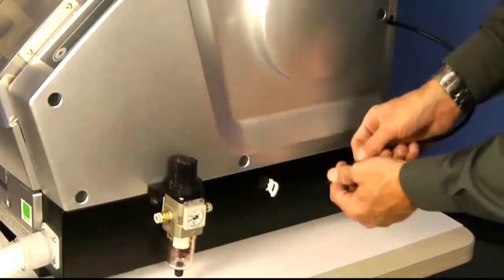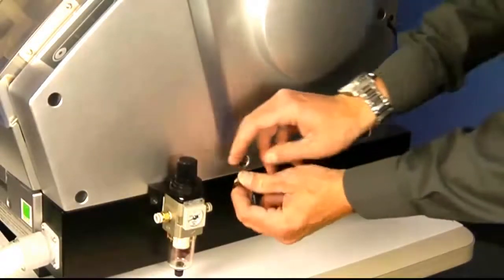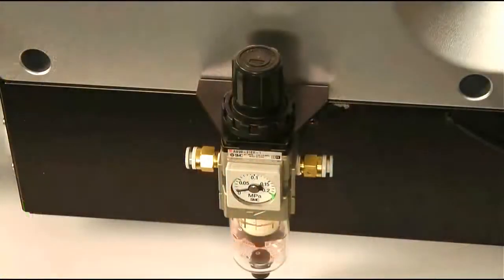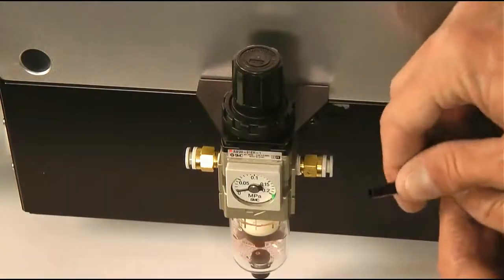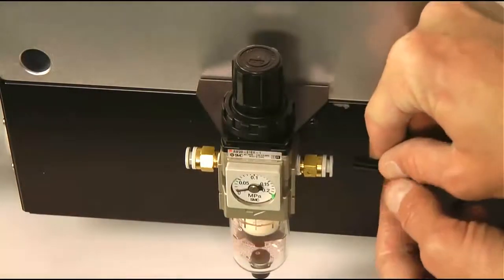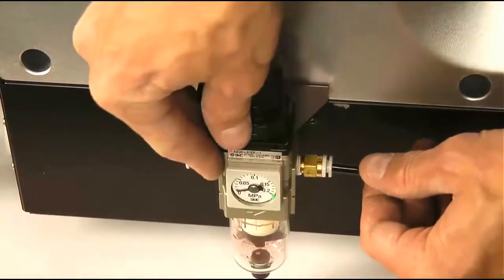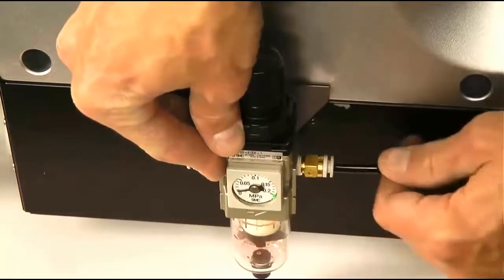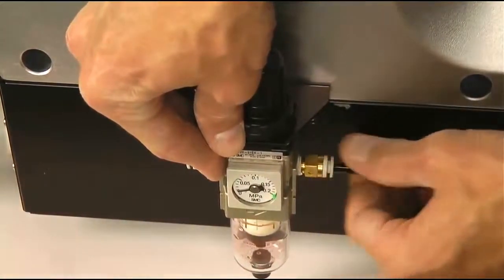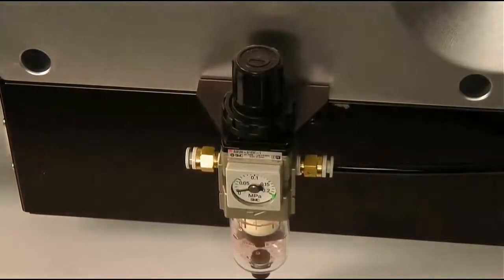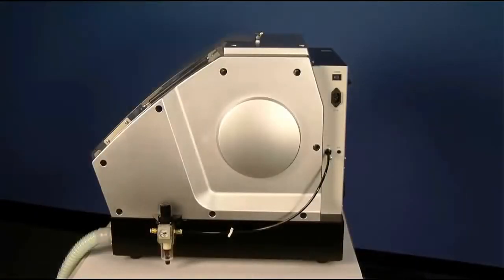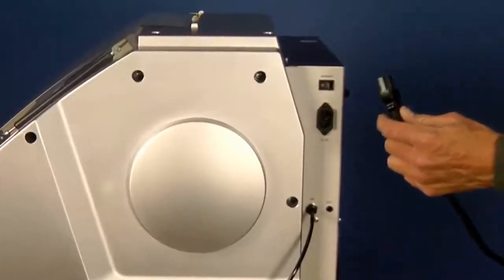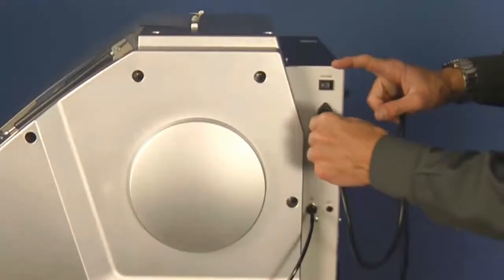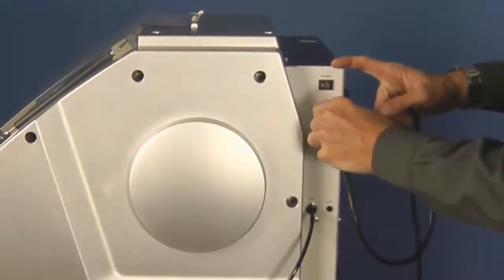Once the regulator is securely fastened, run the polyurethane tubing from the back of the machine through the tube holder and securely place it in the quick connect portion of the air regulator, making sure that you press it firmly into place to create a flush airtight seal. The next step is to plug in your power cord into the outlet located just below the main power switch.